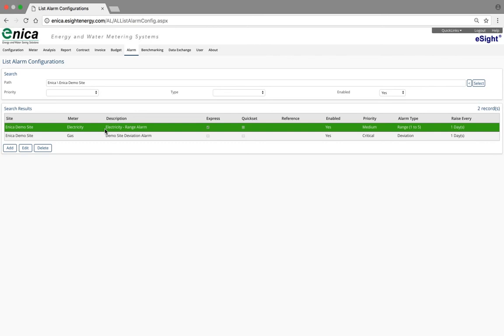based on actual performance away from what we're expecting. So we're saying that if we have a consumption which is the equivalent of 40,000 kilowatt hours more than what we expected for the weather, then we're going to alarm and get to know about that. So this is a very intelligent way of alarms not actually being related to the raw kilowatt hour values or energy values, but more based on driving factors.